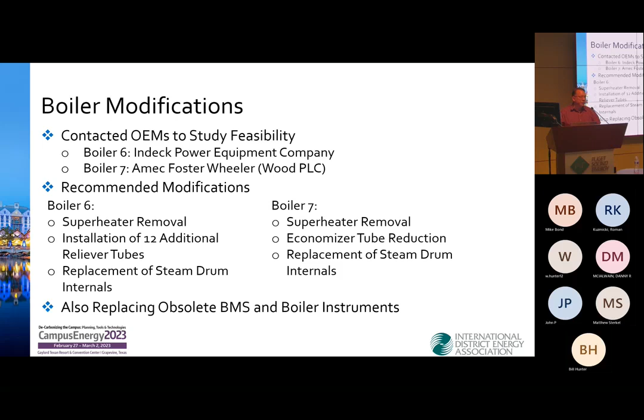So just the idea when I say superheated boiler: superheating is just taking steam and adding more energy to it. Those vertical tubes on the left picture, that's the superheater. Exhaust gas is flowing over those pipes full of steam, raising the temperature, in this case, up to 650 degrees Fahrenheit.